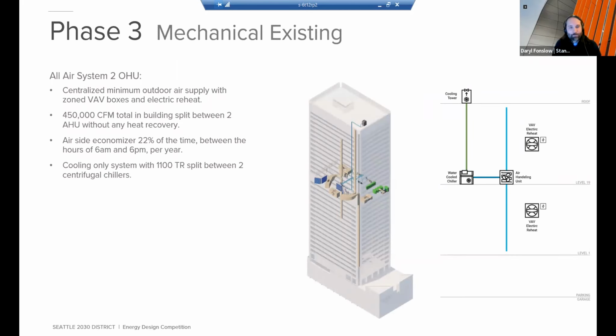Thanks. We took a look at the existing conditions here and tried to find the opportunities. From a ventilation standpoint, there are 2 existing air handling units on level 19, which was really the heart of the building from an HVAC perspective. There were 2 existing centrifugal chillers that had recently been replaced and that we wanted to maintain in our concept. From a heating standpoint, there was electric reheat at VAV boxes distributed on the floor plates.